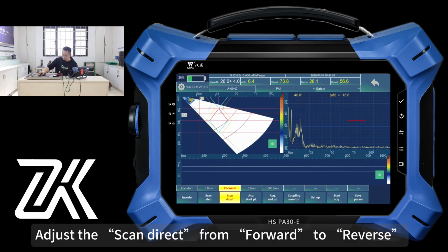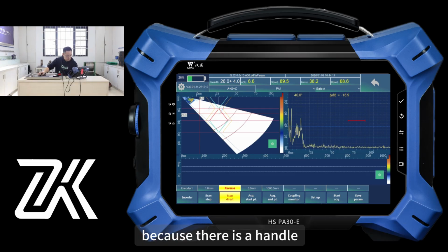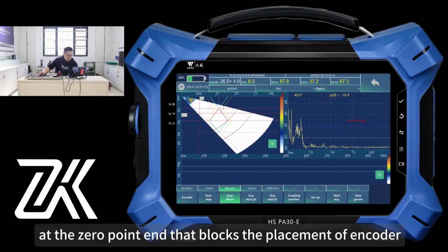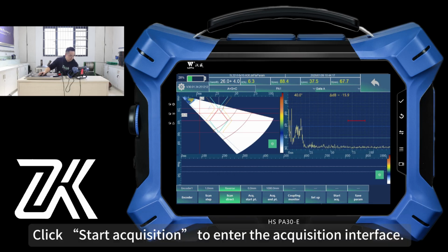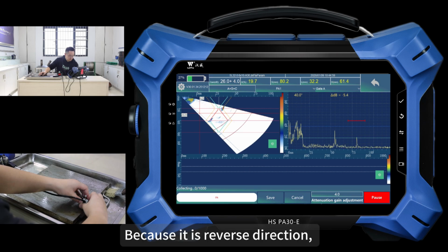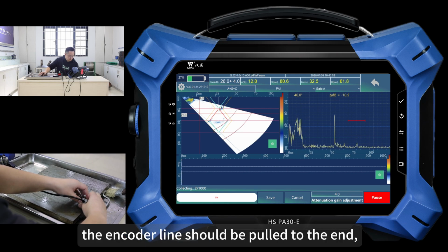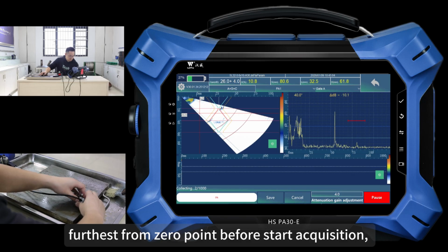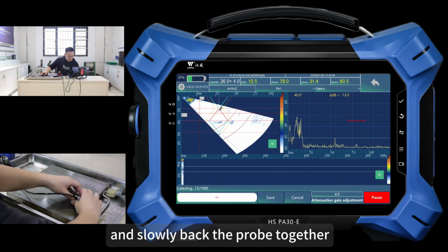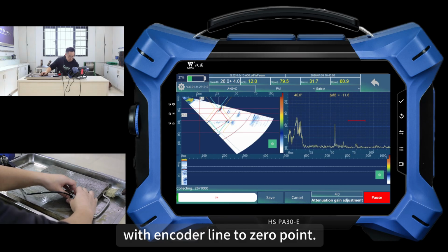Adjust the scan direction from forward to reverse because there is a handle at the 0-point end that blocks the placement of the encoder. Click Start Acquisition to enter the acquisition interface. Because it is reverse direction, the encoder line should be pulled to the end, furthest from 0-point, before start acquisition, and slowly move the probe back together with the encoder line to 0-point.